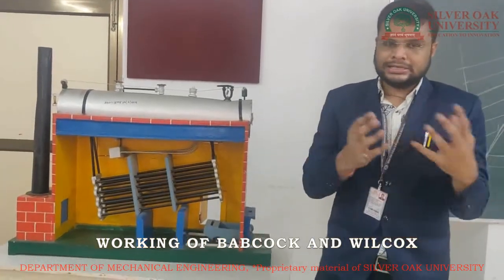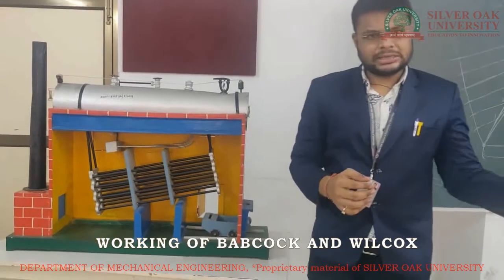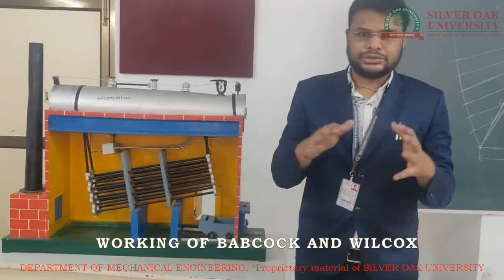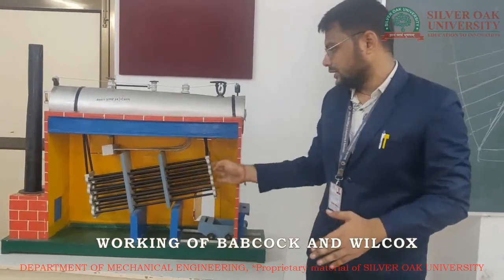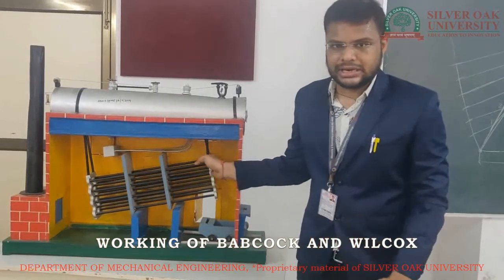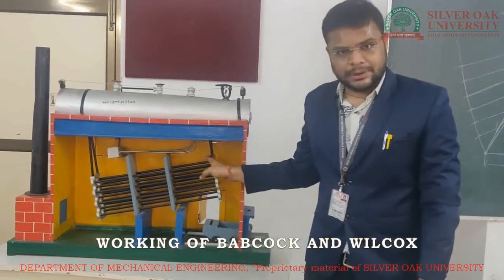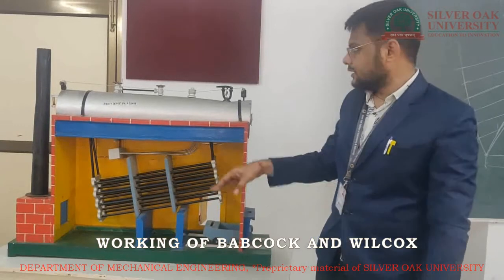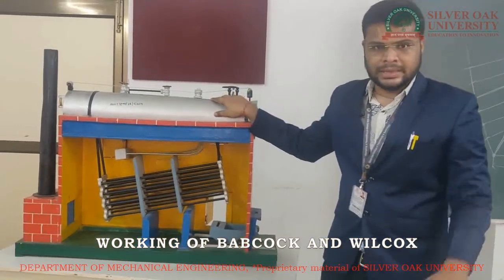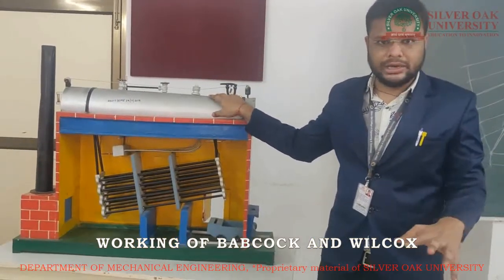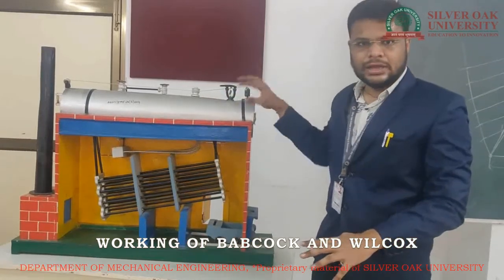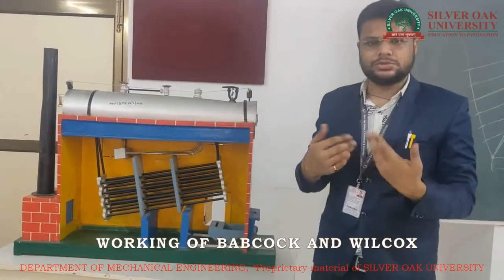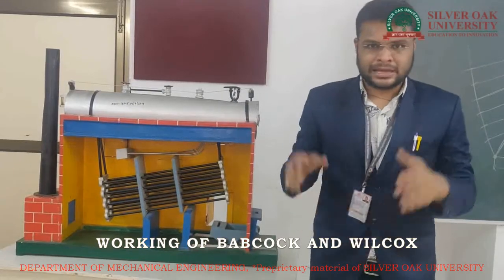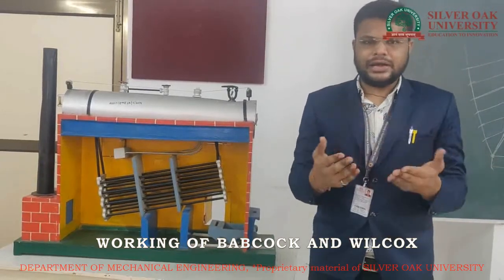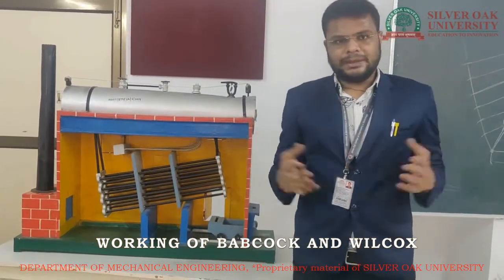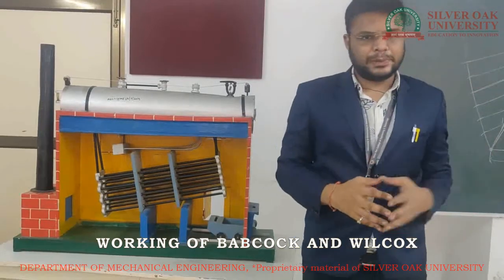And here, as we know, water has a higher density than steam, and due to this density difference, the steam moves to the upper side, to the up take header, and through this up take header it moves to the steam drum. And like other kinds of boiler, the steam is extracted from the steam stop valve, which is used for further applications. The Babcock-Wilcox boiler itself finds a lot of applications in various practices.